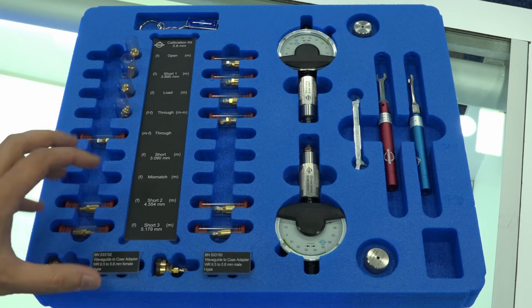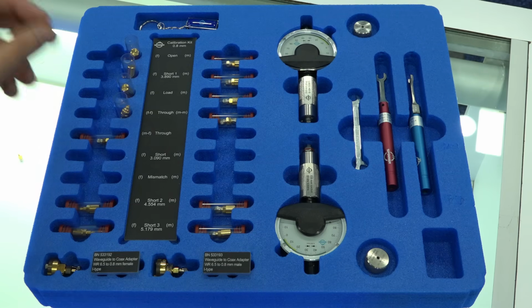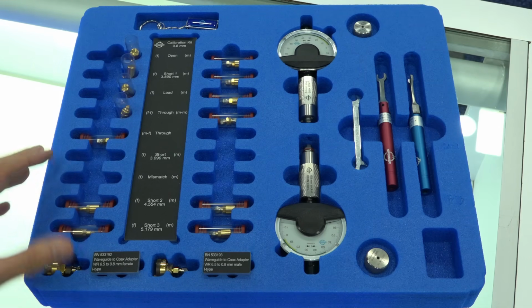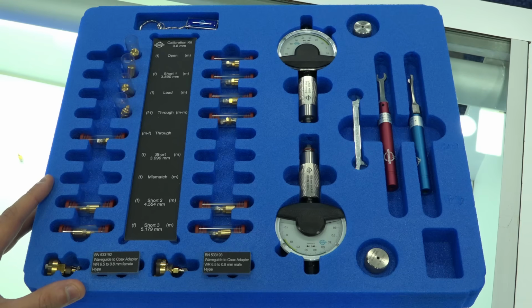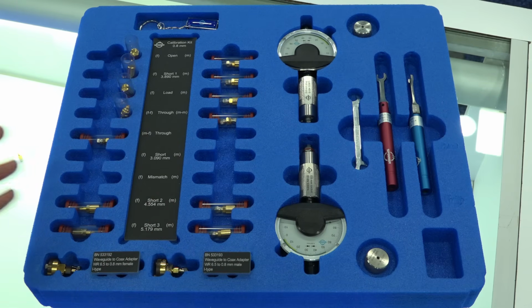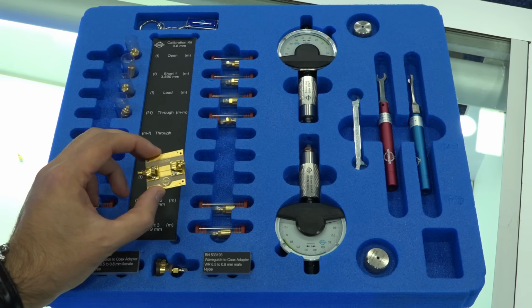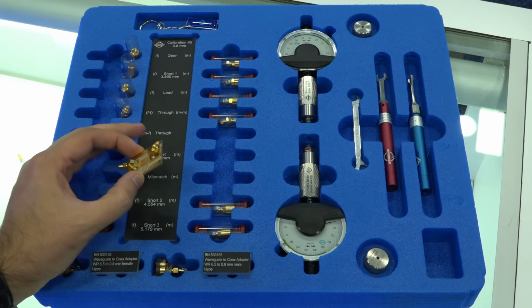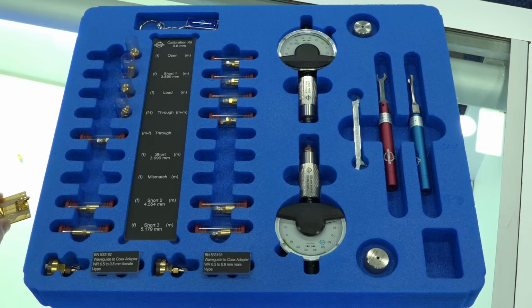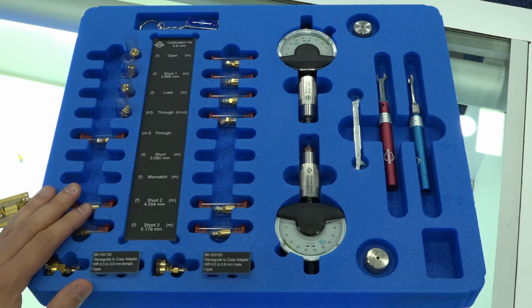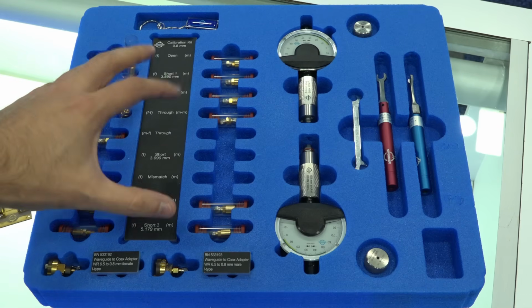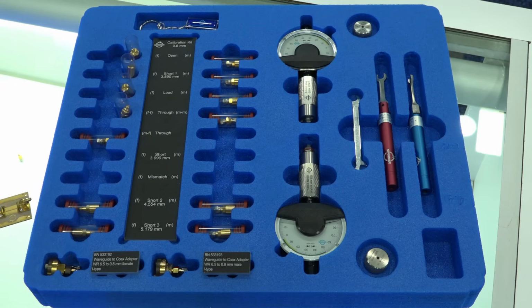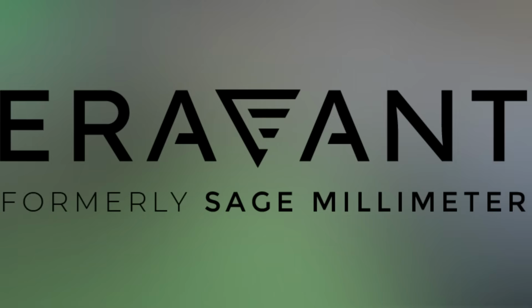So with this traceability, now you can calibrate your coaxial interface, which is needed for these broadband optical devices that people are making, and then cal all the way to 167 gigahertz, and then get a single sweep measurement with traceability in there. And they also have launch connectors like this that allow you to launch directly onto a PCB. Again, these coaxial connectors are critical for this next generation of optical devices. So having something like this, for the new generation of this, it's just inevitable. Somebody has to be able to do this traceable cal so you can characterize these next generation optical components.